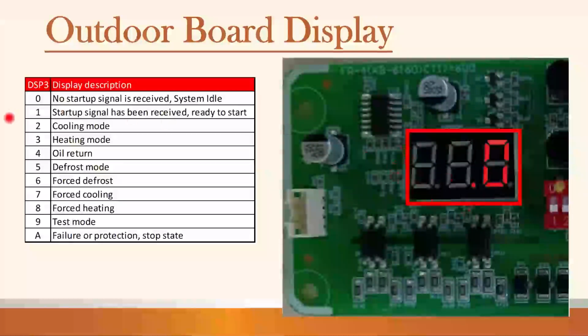During normal operation, this is what you'll see. 0 means no startup signal is received, system idle. So it'll say 0. If it says a 2, we are in cooling mode, 3 heating mode, 4 oil return, 5 defrost, and so forth. So that is in the manual, so you can refer to that if you're curious what those modes mean. Of course, A will be a failure or protection stop state. So if you see an A on there, something's wrong.